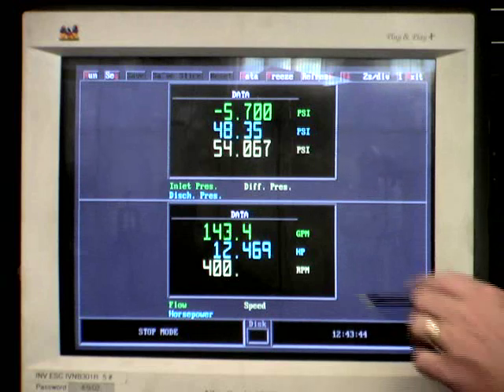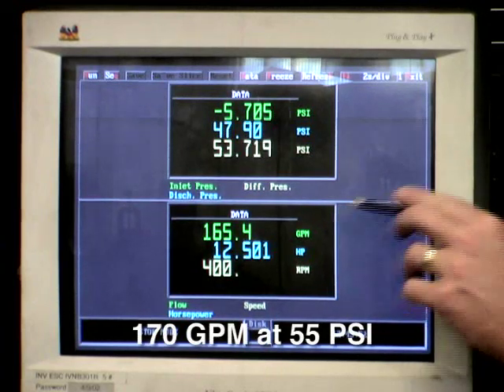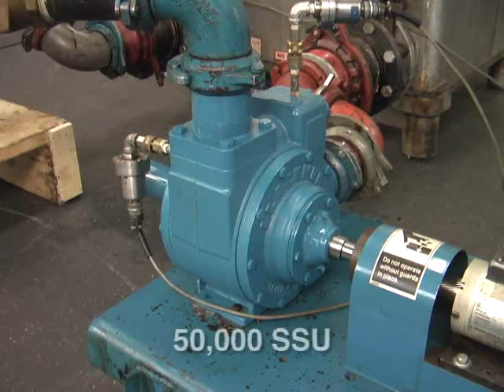As we increase the speed to 400 RPM, the pump delivers 150, 160, almost 170 gallons per minute at 55 PSI. This demonstration illustrates that vane technology performs very effectively in moving high-viscosity liquids — in this case, 50,000 SSU — at both high and low speeds.